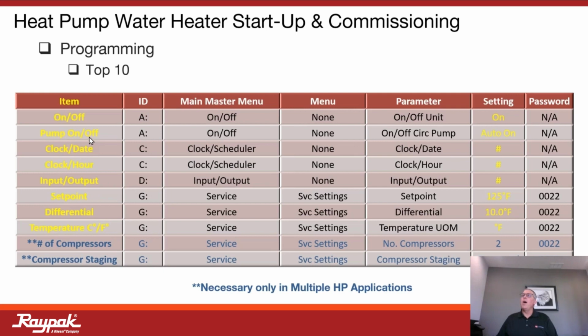Okay, on-off for pump. Even though you would think that the default would be on if I'm landing the wires to my pump, I still have to go into the programmable feature and say, hey, I do have a pump attached that my pump contactor is controlling. Let's go ahead and enable it.